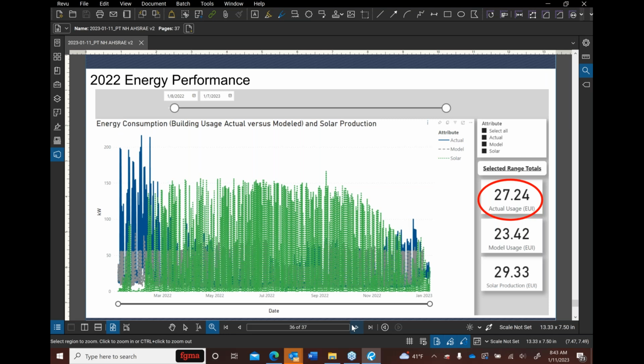So when we were starting to look at this, in blunt words, we're kind of freaking out a little bit. Why are we using so much more energy than what we had anticipated? And there were 2 real causes to that. One is the one that we had mentioned before, that we were using the electric resistance heat in the dedicated outside air systems as opposed to the heat pump heat. And then secondly, the building automation system was not aligned with the utility, and the utility was reporting incorrectly. And so that impacted our total energy usage, and we're working on correcting that now. But as you can see, even with those 2 poor performing months of January and February, if you look over to the right, our actual usage had an EUI of 27.24, and our solar production for a full year was 29.33. So even with those poor performing months, we are still officially net zero for the year.